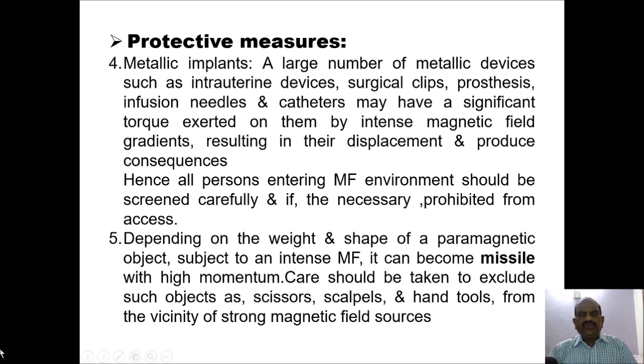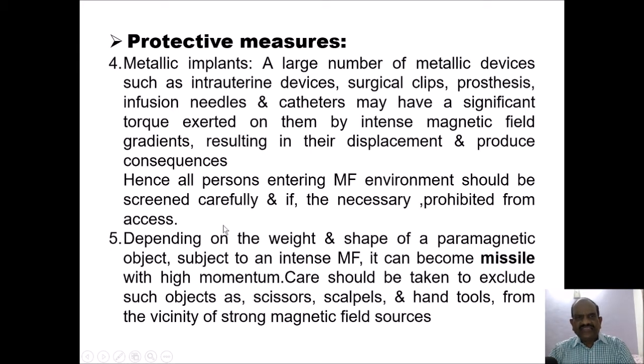Many other important protective measures must be followed. A large number of metallic devices such as intrauterine devices, surgical clips, prostheses, infusion needles, and catheters may have significant torque exerted on them by intense magnetic field gradients, resulting in their displacement with serious consequences. Hence, all persons entering a magnetic field environment should be screened carefully and, if necessary, prohibited from access. Depending on the weight and shape of a paramagnetic object subject to an intense magnetic field, it can become a missile with high momentum. Care should be taken to exclude objects such as scissors, scalpels, and hand tools from the vicinity of strong magnetic fields.